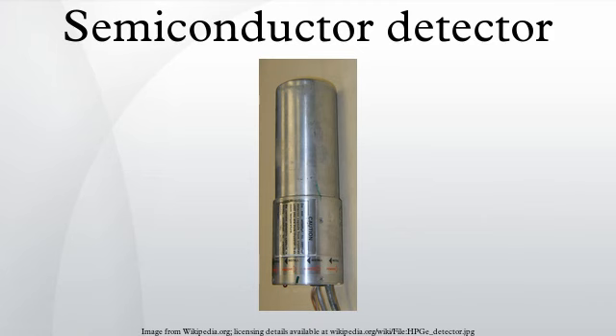Consequently, germanium crystals were doped with lithium ions in order to produce an intrinsic region in which the electrons and holes would be able to reach the contacts and produce a signal. When germanium detectors were first developed, only very small crystals were available. Low efficiency was the result, and germanium detector efficiency is still often quoted in relative terms to a standard 3×3 inch NaI scintillation detector. Crystal growth techniques have since improved, allowing detectors to be manufactured that are as large as or larger than commonly available NaI crystals, although such detectors cost more than $100,000.